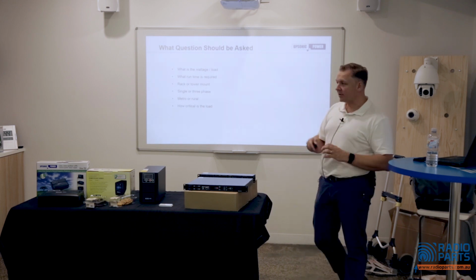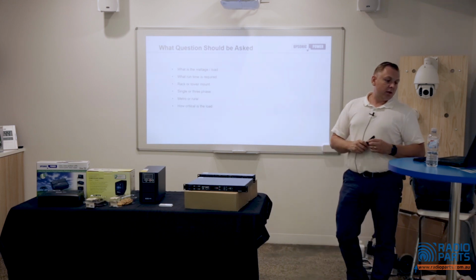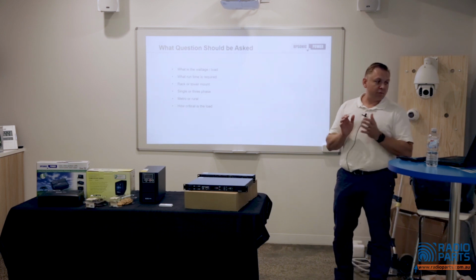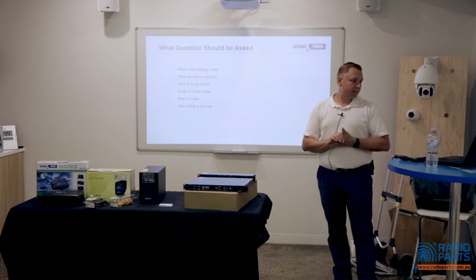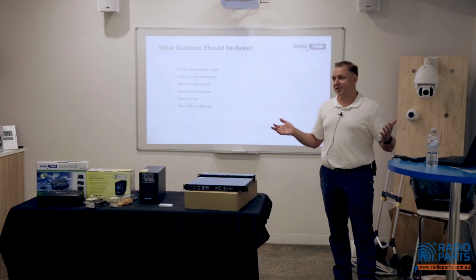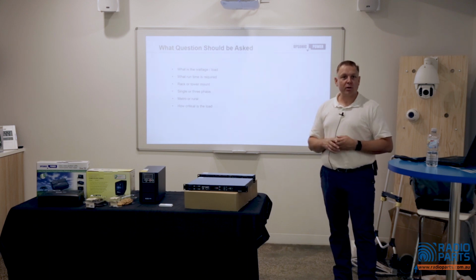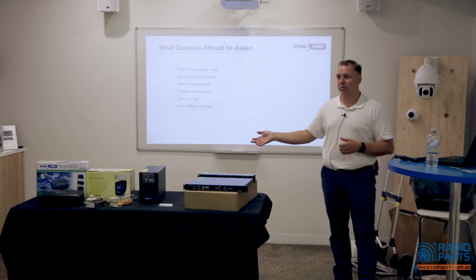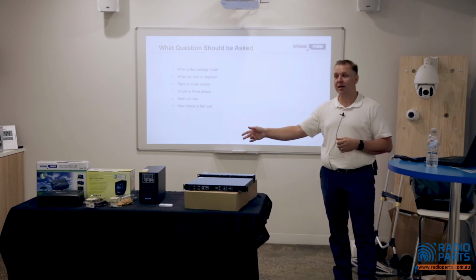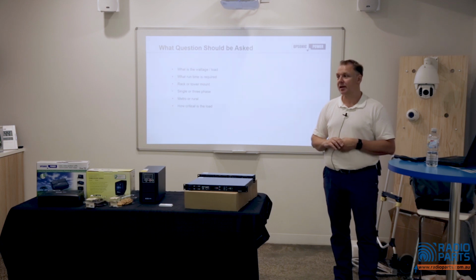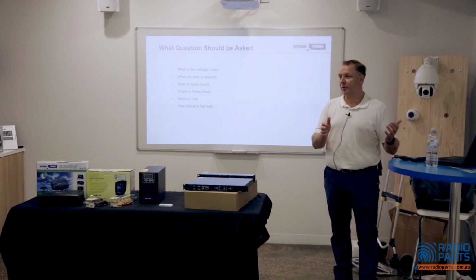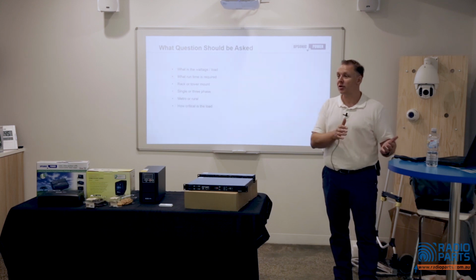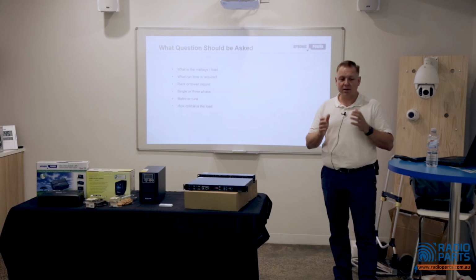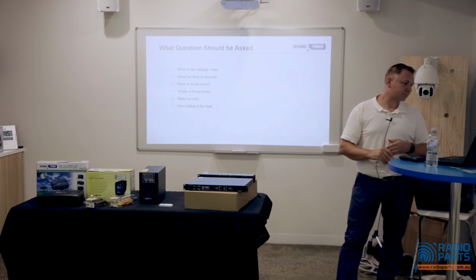Okay, this is the critical stuff for you guys. The questions you need to ask from your customer when they want a UPS. What's the load? That's pretty basic. Typically, we want to size the UPS at no more than 80% of its load. So, if it's a 1 kVA UPS, and we've got 900 watts in this case, we really don't want to give them anything more than about 750 watts onto the UPS. Allows a little bit of expansion and that sort of thing as well.